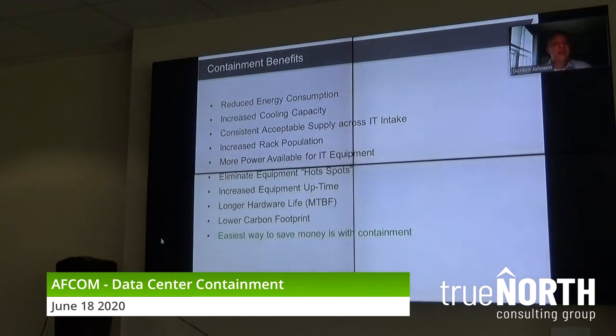The other thing that falls under the definition of cooling optimization, I want to match the cooling capacity, that's the airflow and CFM that I'm providing to you, with the IT cooling demand. For instance, if your IT equipment says, my fans demand 50,000 CFM, well, that's great. I don't want to give you 100,000 CFM. I don't want to give you more. I want to match that 50,000 demand with as close to possible 50,000. I'm going to go a little bit higher, but I just want to get higher supply versus the demand. That's what the definition is of cooling optimization.